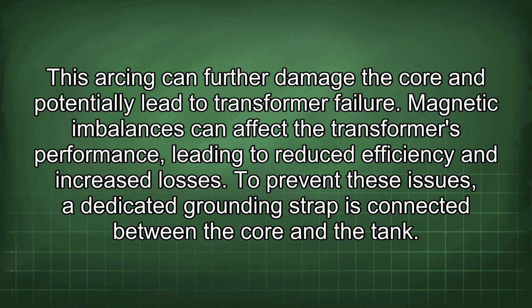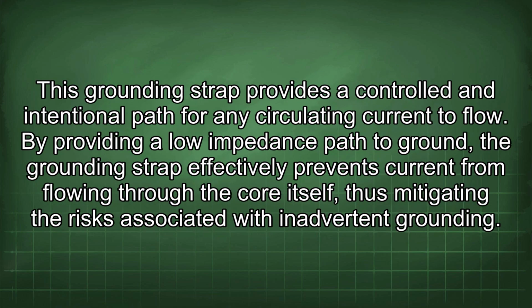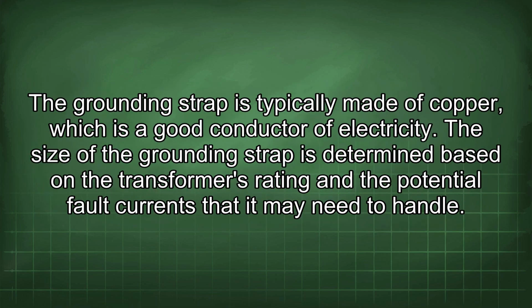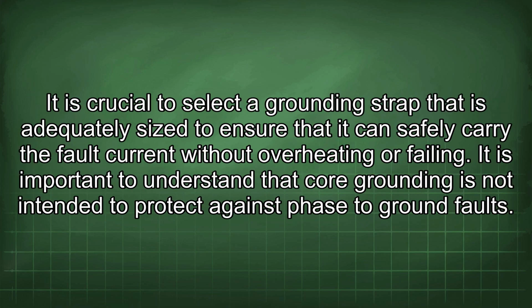To prevent these issues, a dedicated grounding strap is connected between the core and the tank. This grounding strap provides a controlled and intentional path for any circulating current to flow. By providing a low impedance path to ground, the grounding strap effectively prevents current from flowing through the core itself, thus mitigating the risks associated with inadvertent grounding. The grounding strap is typically made of copper, which is a good conductor of electricity. The size of the grounding strap is determined based on the transformer's rating and the potential fault currents that it may need to handle. It is crucial to select a grounding strap that is adequately sized to ensure that it can safely carry the fault current without overheating or failing.